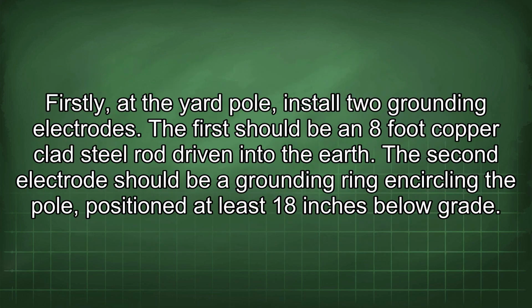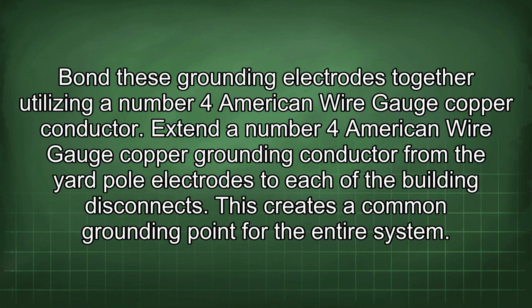Firstly, at the yard pole, install two grounding electrodes. The first should be an 8-foot copper-clad steel rod driven into the earth. The second electrode should be a grounding ring encircling the pole, positioned at least 18 inches below grade. Bond these grounding electrodes together utilizing a number 4 American wire gauge copper conductor.